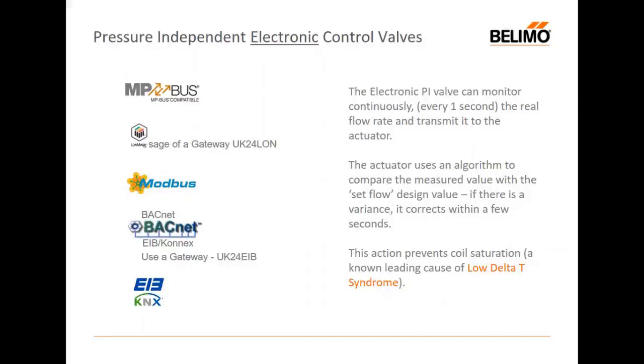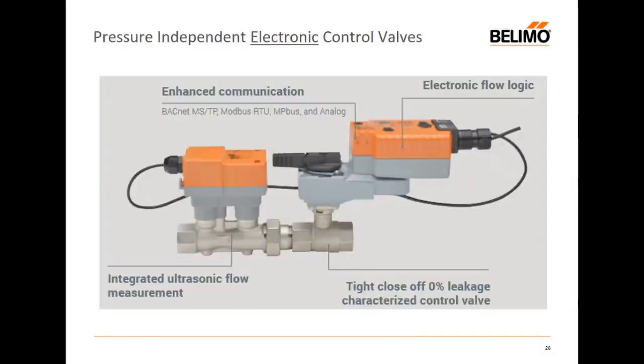So this action of preventing coil saturation is a very good tool in addressing one of the leading causes of low delta T, which is coil saturation, overflow. You don't see it, it's invisible. So what does one look like typically?